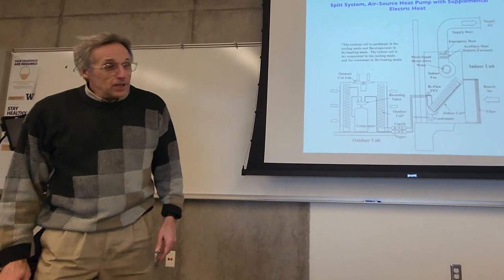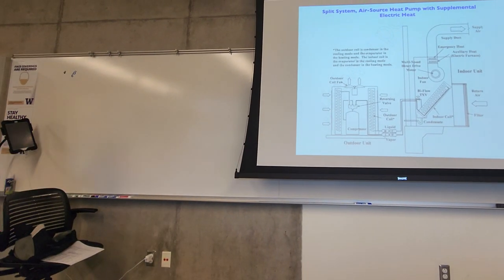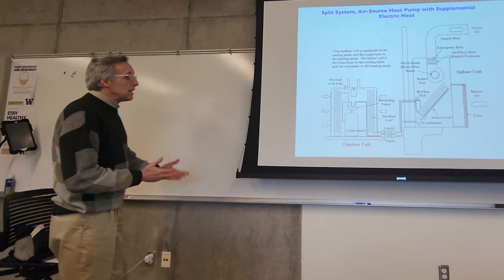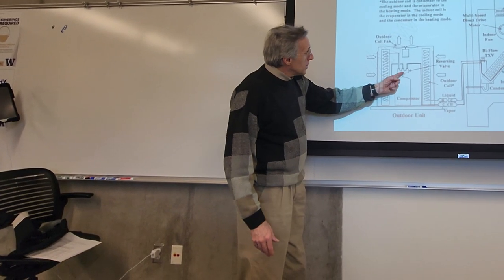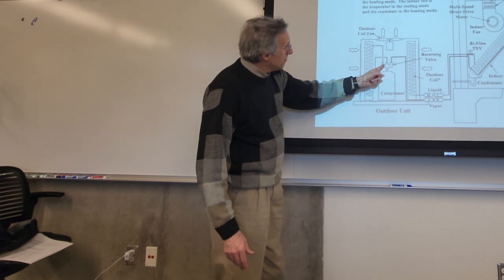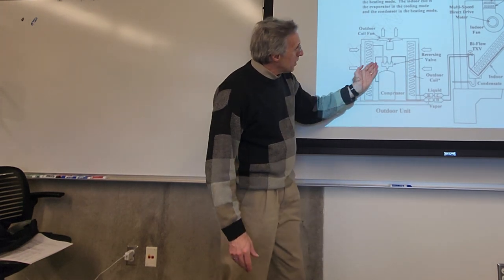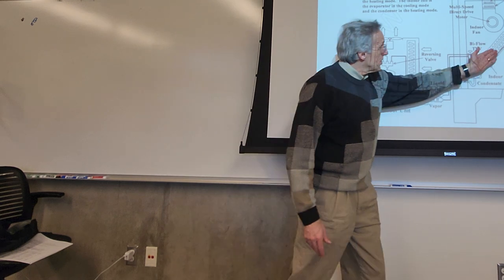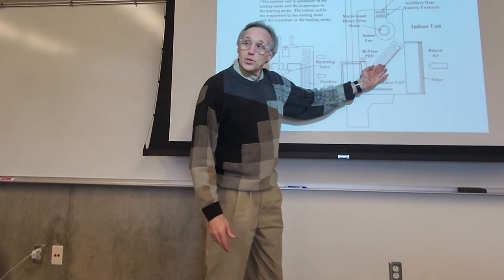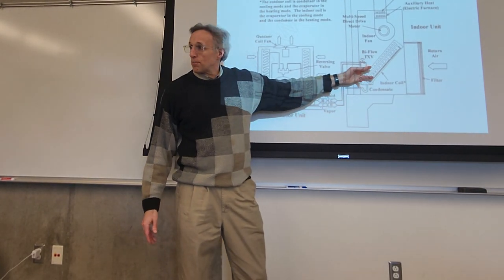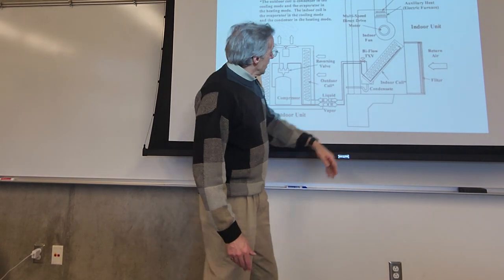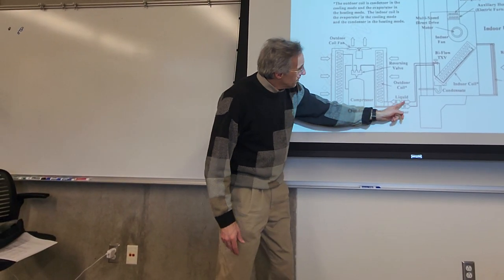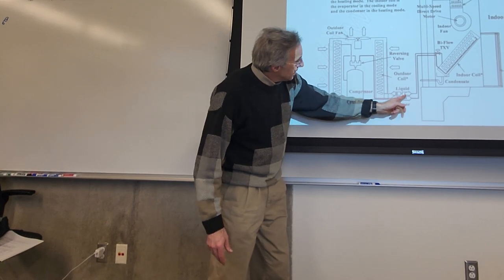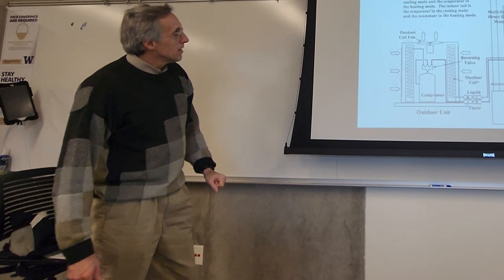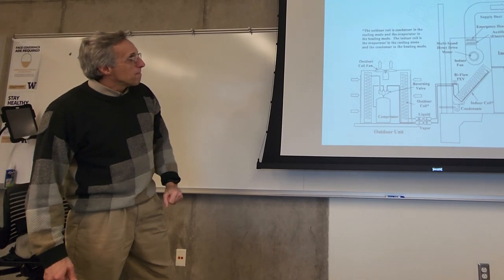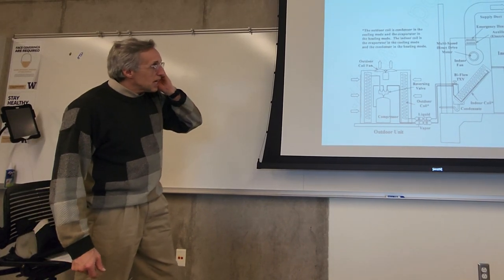And then we go up a step, we can get to the heat pump. We saw last time, this is a heat pump that can be used for heating and cooling, so it has the reversing valve that allows you to change the direction of refrigerant flow, so that this is a condenser in the winter when you want heat, and an evaporator in the summer when you want cooling. And you can see showing the different directions for heating and cooling. But everything else is pretty much the same.